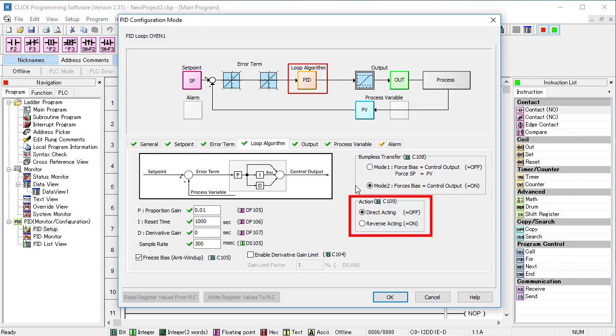Do we have a direct or reverse acting system? That is, when we increase the output, does the process variable – or temperature in our example – go up? Ours does, so we have a direct acting system. If the temperature went down when the output went up, like in a cooling system, we would select reverse acting.